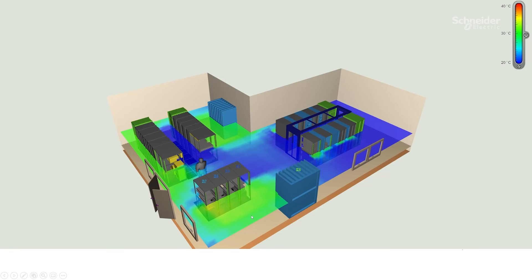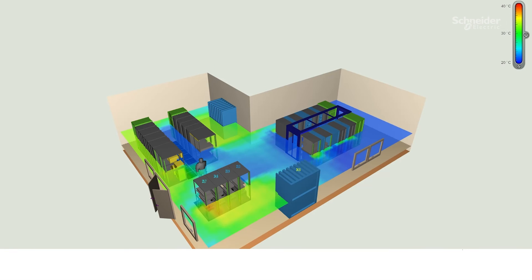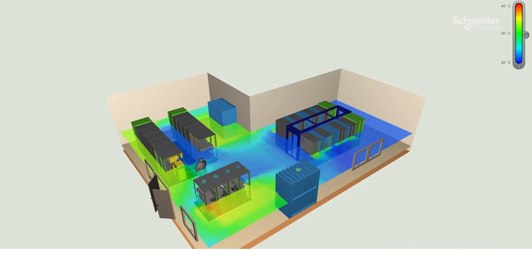If I switch to 22 degrees, I see the change, but as you can probably recognize, the change is so minimal that we actually are able to operate this data center with that new setting of 22 degrees supply temperature without any risk to the operation of our data center.